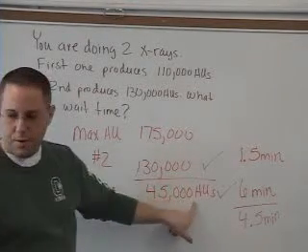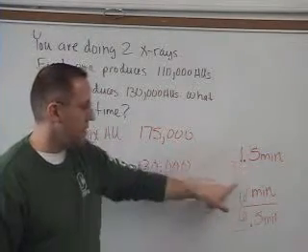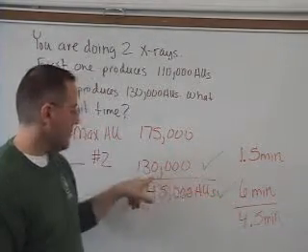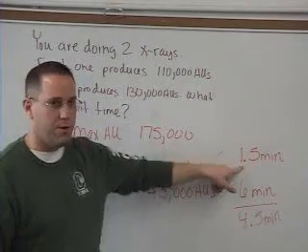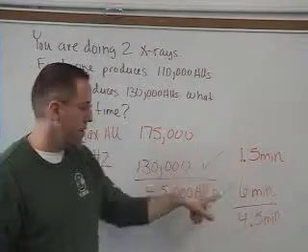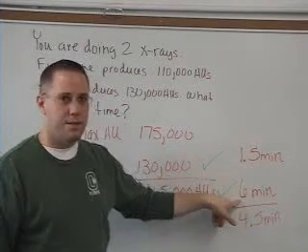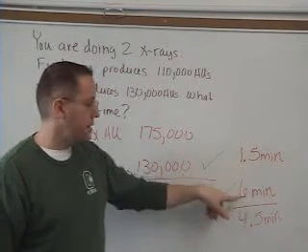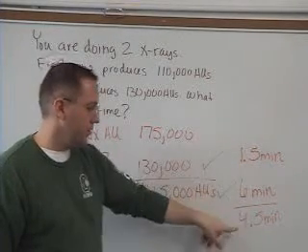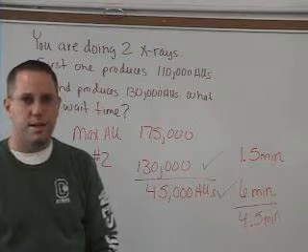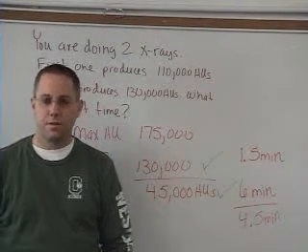Look those values up on the chart on page 81 and see what time corresponds to each one. For 130,000 heat units, you get a time of 1.5 minutes. For 45,000 heat units, you get a time of six minutes. Then you take the higher number — six minutes — minus the smaller number, and you get the difference. That's how long you're supposed to wait from one x-ray to the next one.